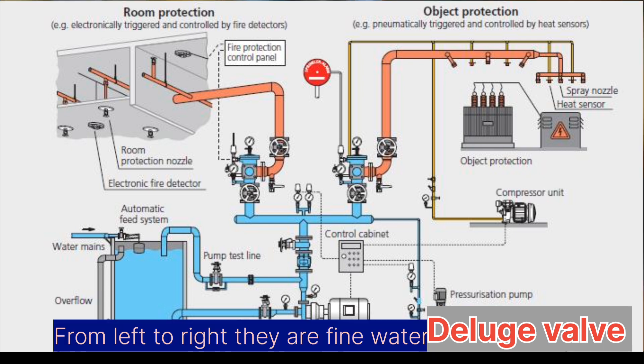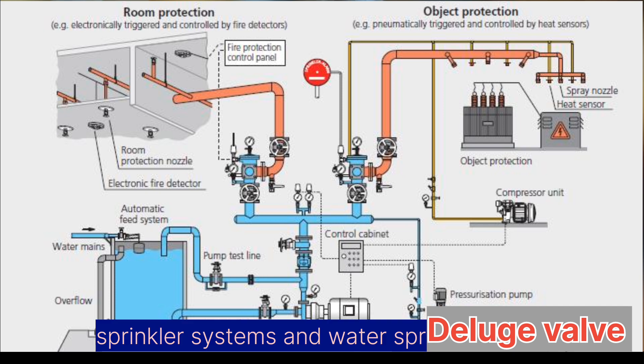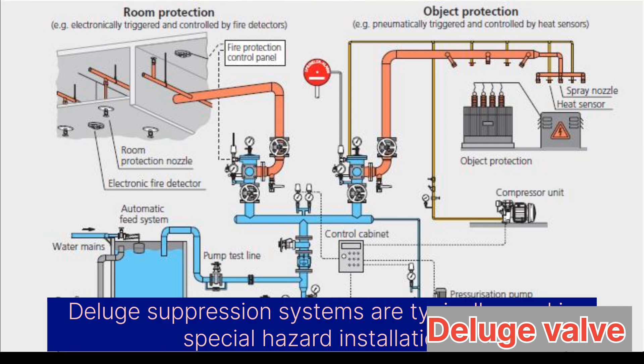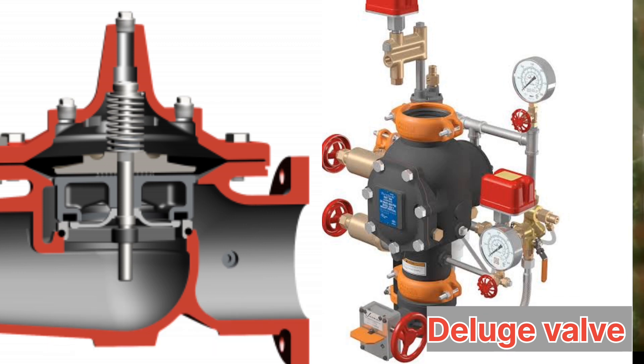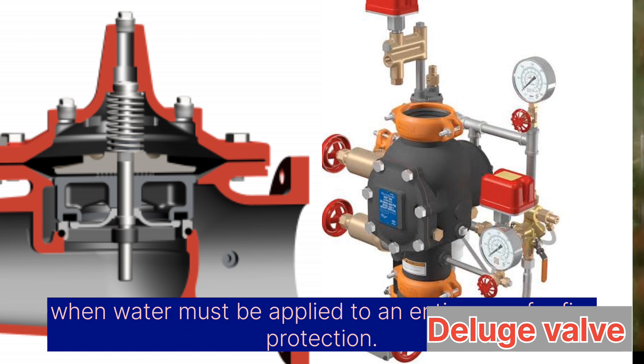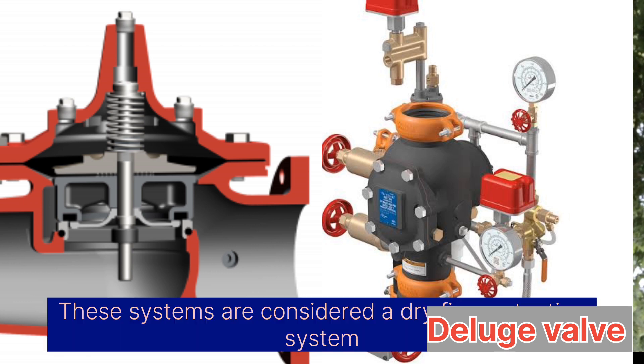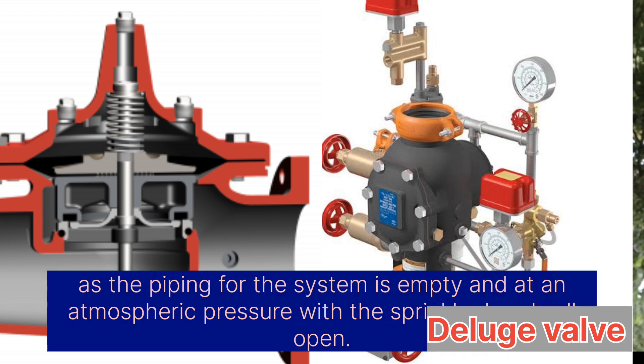From left to right, they are fine water spray systems, sprinkler systems, and water spray systems. Deluge suppression systems are typically used in special hazard installations when water must be applied to an entire area for fire protection. These systems are considered a dry fire protection system, as the piping for the system is empty and at atmospheric pressure with the sprinkler heads all open.